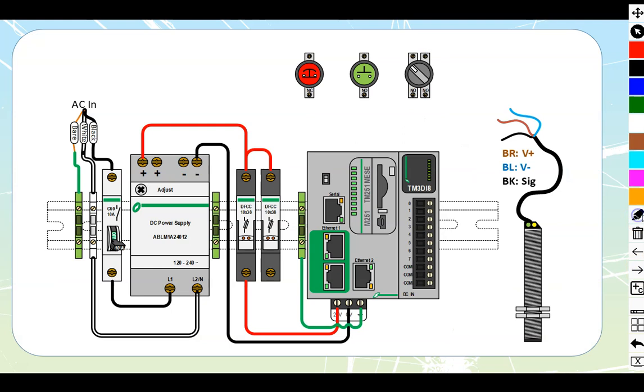Okay, so now we've got a PLC set up. Let's just go over some components on it real quick. And then we'll start the actual connections. First thing that we see is that we have AC being brought in onto my distribution blocks here on the DIN rail. I've got my neutral, I have my bond, I have a small DIN rail circuit breaker. I'm taking that AC in. I'm feeding that into a DC power supply. And I'm converting that into 24 volts DC over here. That 24 volts DC, I am then feeding the positive out into a set of DIN rail fuses. One of these sets of DIN rail fuses provides power all the way into my main PLC body. This is my PLC brain. It's an M251 that we have over here with some serial Ethernet communications and stuff on board. And the M251 class does not have on board inputs and outputs. It's simply a brain. And we always have to attach these expansion modules to it. This is the expansion module we are going to be wiring to it - the first one, which is going to be my inputs. And any additional ones would just get added onto the side right next to that. So we're only putting one on here for this one.